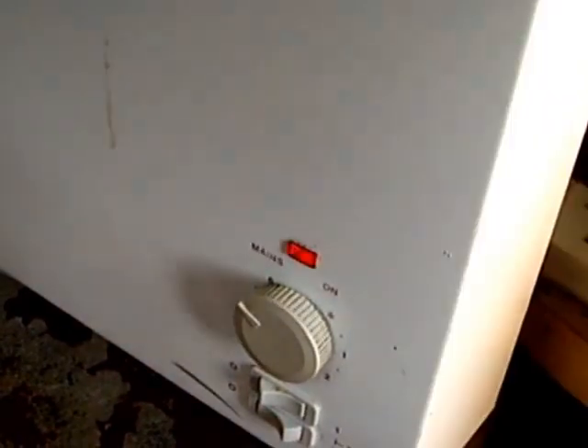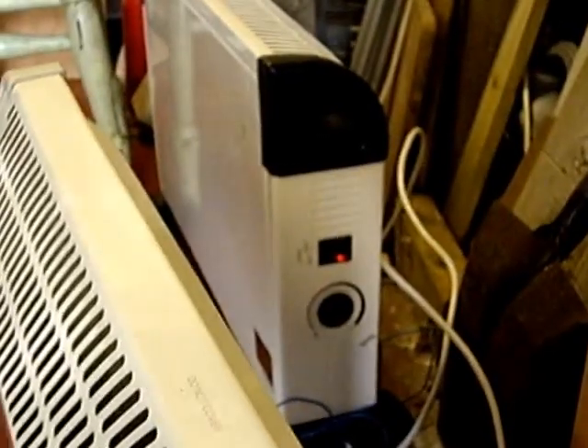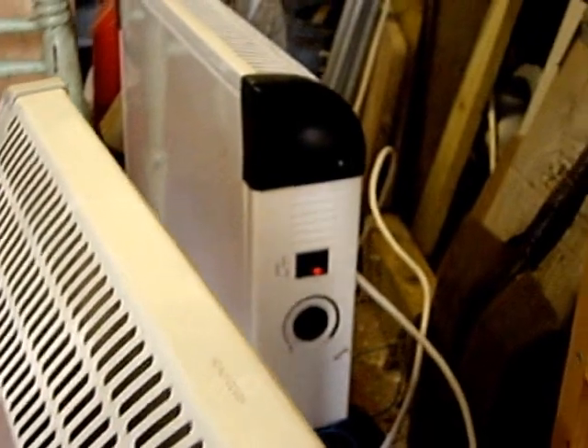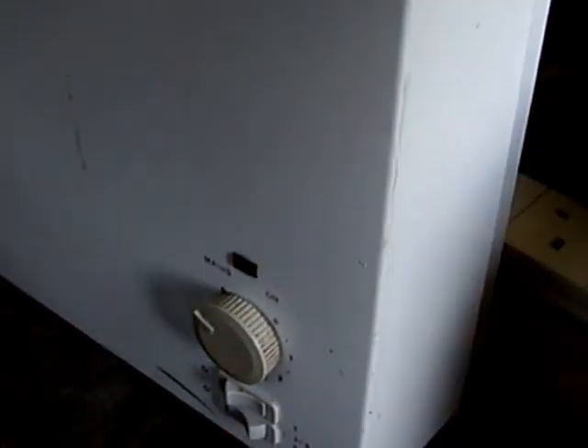So on our remote load, we've got a one kilowatt heater and a 60 watt bulb, which is more than the 750, which is over there, is generating. So this is going to be flicking on and off at the ratio between 1060 and 750 or something like that, which looks about right.